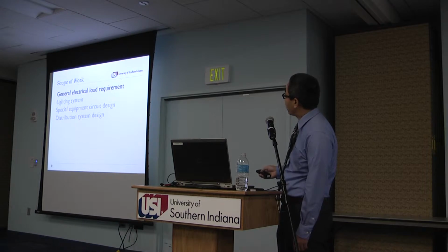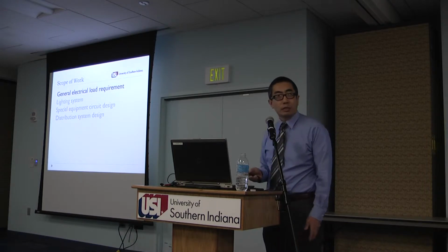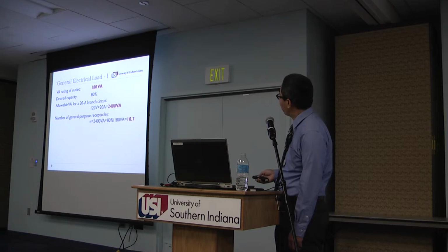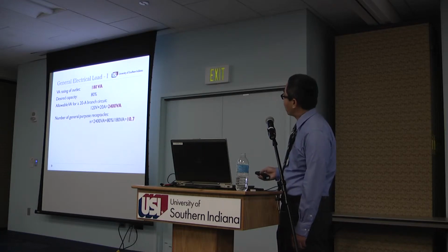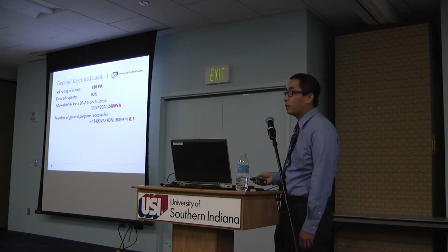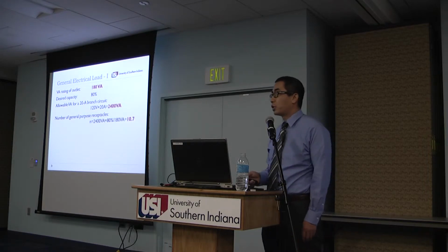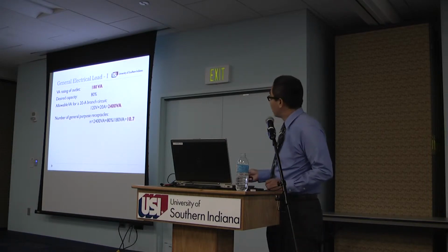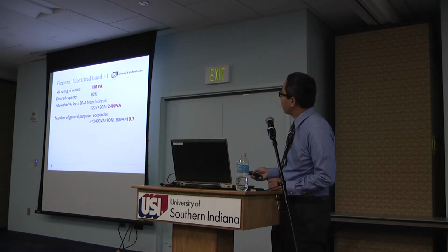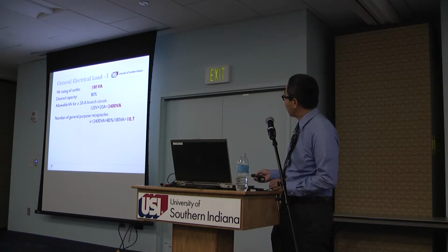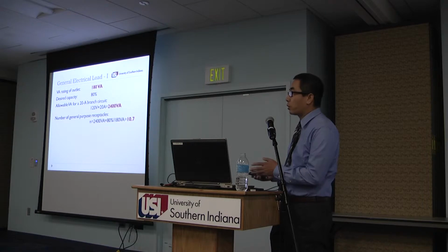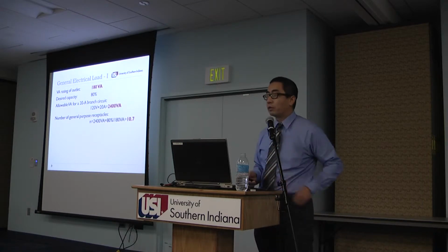So first we need to do the general electric load design. That's basically the receptacles of the shop. And the code asks us to design for a single receptacle at 180 volt-amps. So if we have a 20 amp circuit, we need to calculate how many receptacles we can fit on one circuit. For this calculation, we leave a little bit of wiggle room, so we use up to 80% of the circuit capacity. That leaves us about 10.7, so we put 10 or 11 receptacles on the same circuit. It won't overload the system.